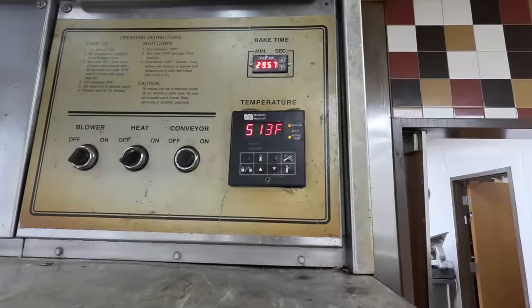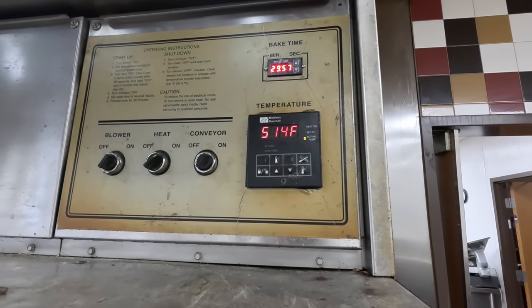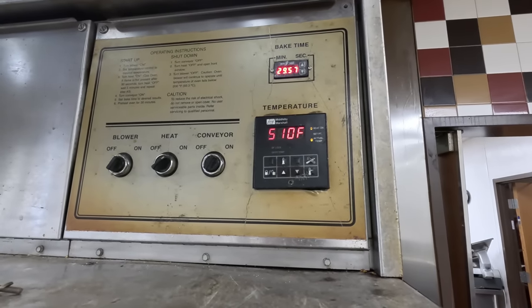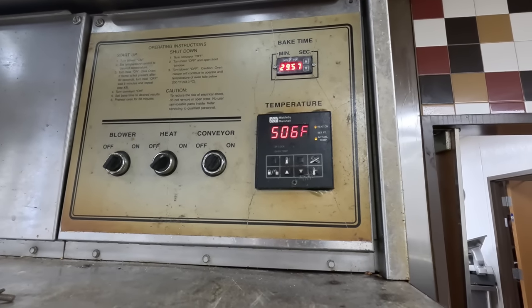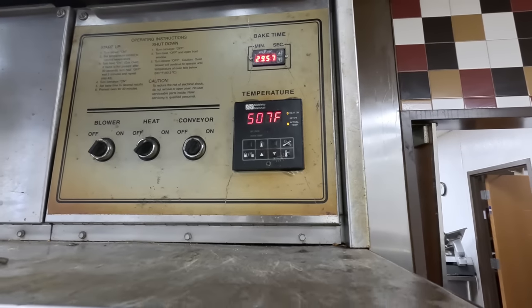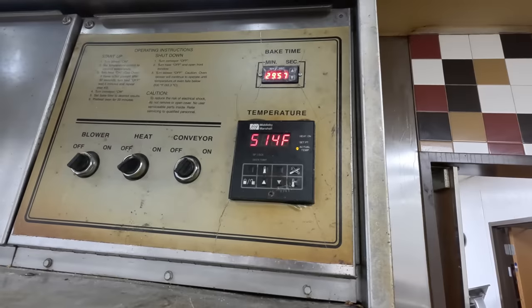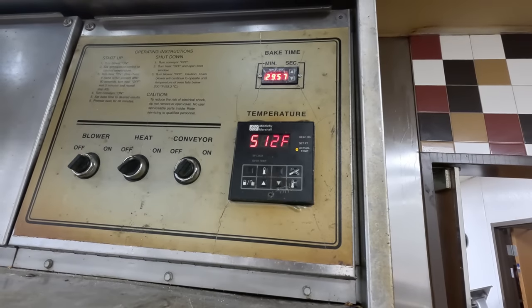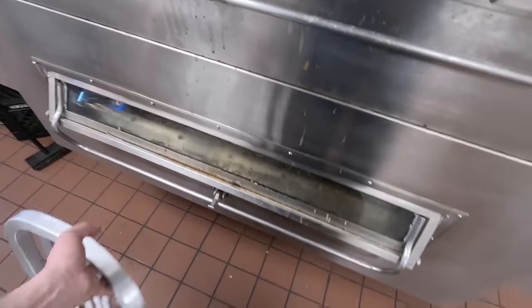Let's wait until she gets up to temp. We just hit set point — just shut off. This is where it'll usually act up. The burner comes right back on immediately. I lost that heat really fast, probably because they're sucking everything out of the building. A lot of three-degree variance. Dropping — comes right on.